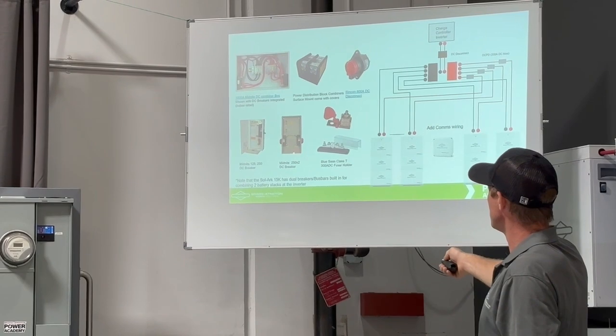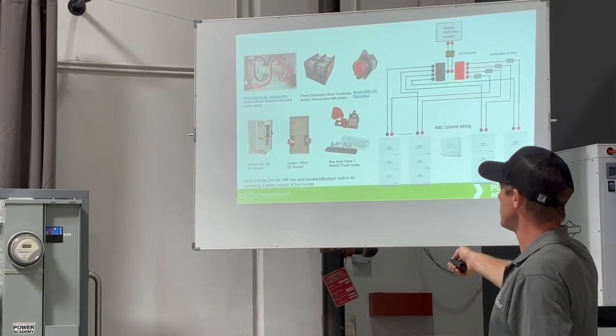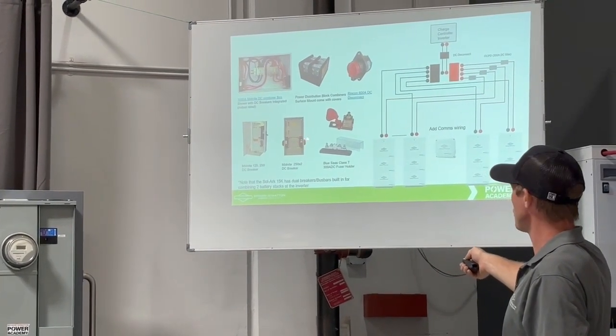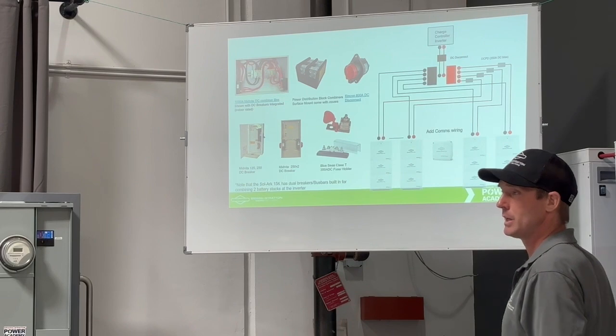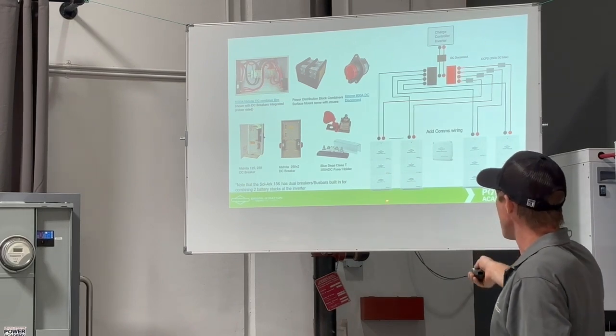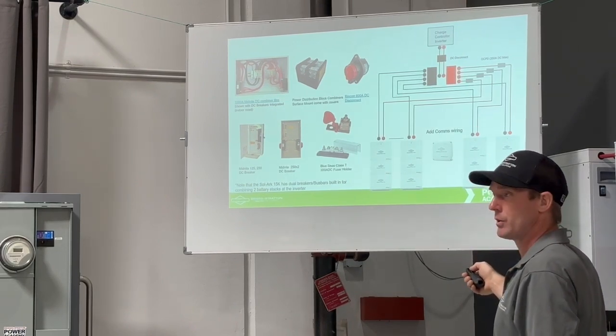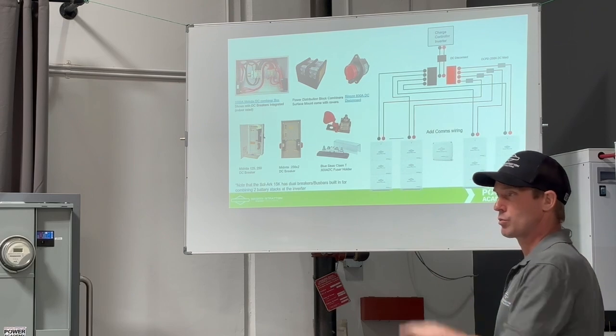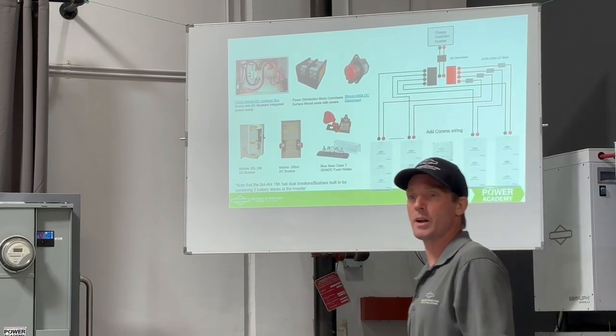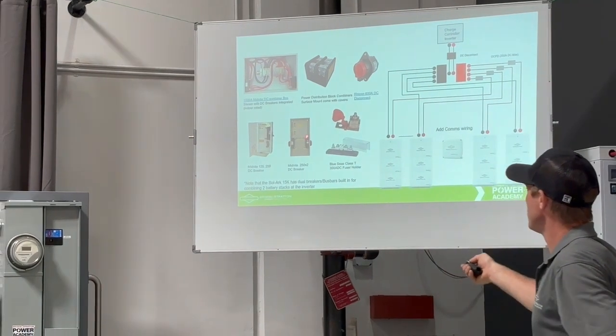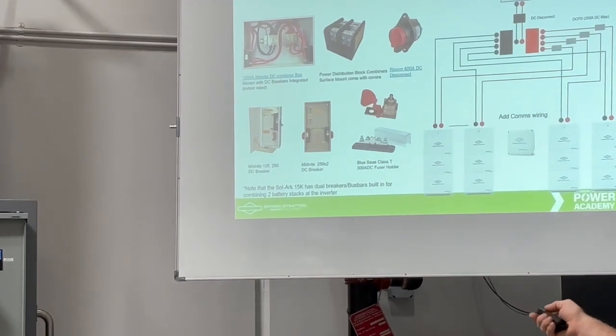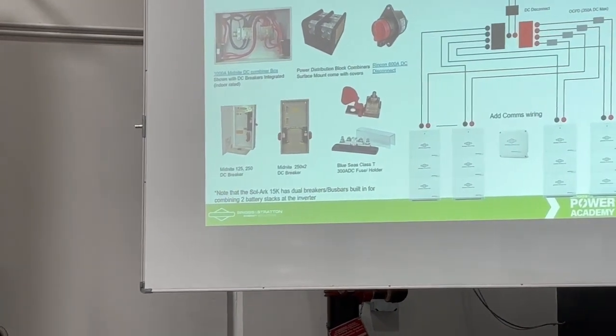Another option is the MidNite 250 by 2, so you've got 2 250 amp breakers coming into that. Each battery stack is capable of 275 amps, so 250 is right about the right range, but it's a little too small for 3 or 4 stacks. I'll show you another option.